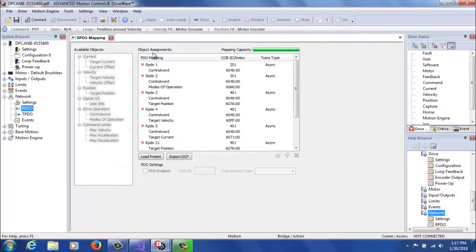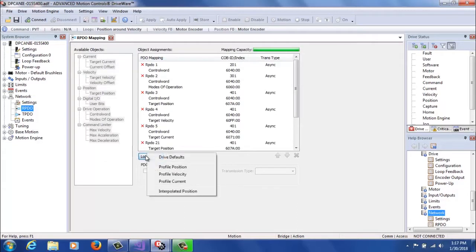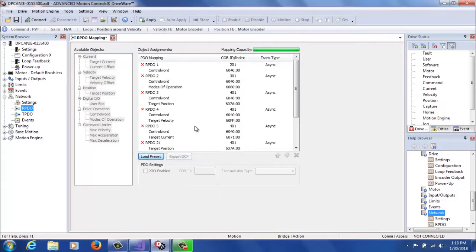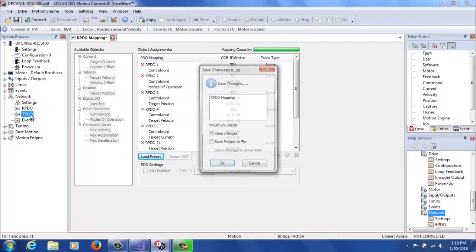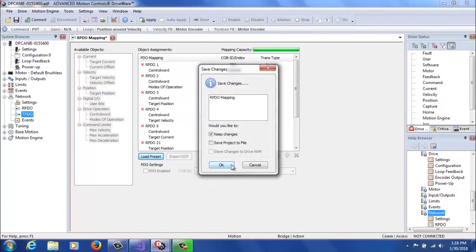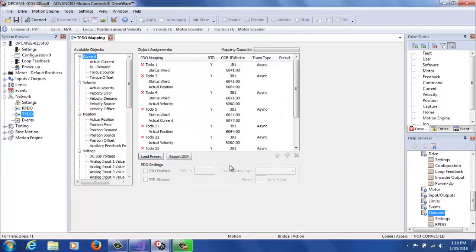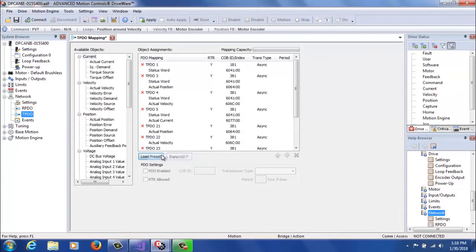For the addresses, if you change that, you're also going to want to go to RPDO and load preset drive defaults, so that all the default COB IDs get loaded properly, and you don't have overlapping RPDOs on a network. You'll do the same thing for TPDOs, and you'll load preset drive defaults.